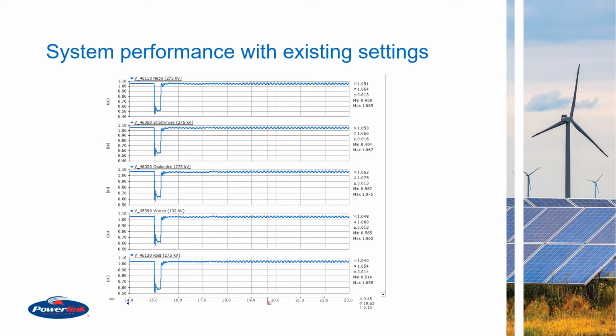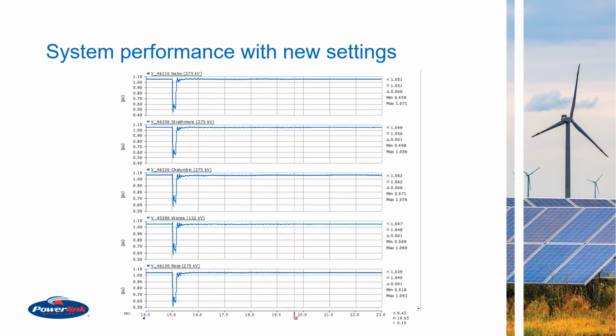And what we can see after fault clearance is oscillations in the voltage, showing that there are some control interactions. And when the new control system of those IBRs is put in place, we can see it helps minimize those control interactions, and we can't really see any oscillations in the voltage.